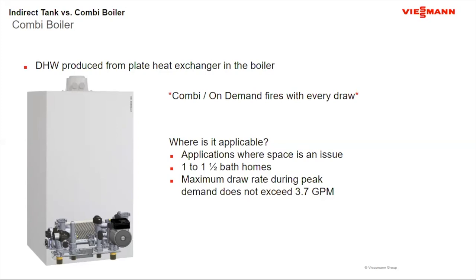And again, from a combi standpoint, what's your draw rate? If your peak draw is in that range of maybe 3.5 to 3.7, again, you can get away with a combi boiler with an input of about 150,000. It shouldn't be significantly oversized for the application. These three bullets usually are my discussion points with somebody when they ask about a combi boiler, as far as whether I do a combi or an indirect water heater. And this is the area where the combi boiler does shine.